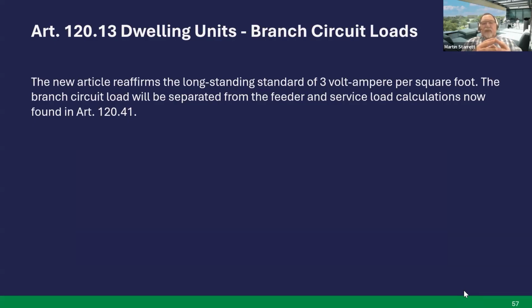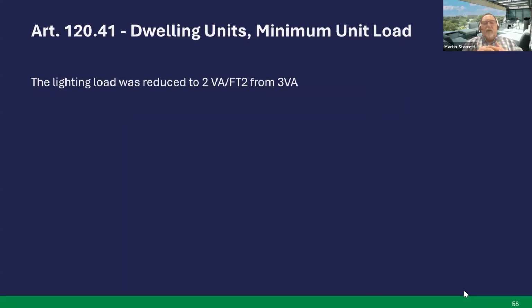120.13 dwelling unit branch circuit loads. The new article reaffirms the long-standing standard of 3 volt amps per square foot. The branch circuit load will be separated from the feeder and service load calculations now found in Article 120.41. So when I show you 120.41, the VA per square foot will change. But when you're figuring branch circuit loads, it'll stay at the 3 VA that it has been for years. Next slide.